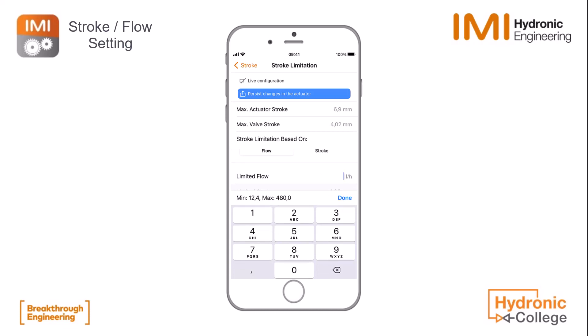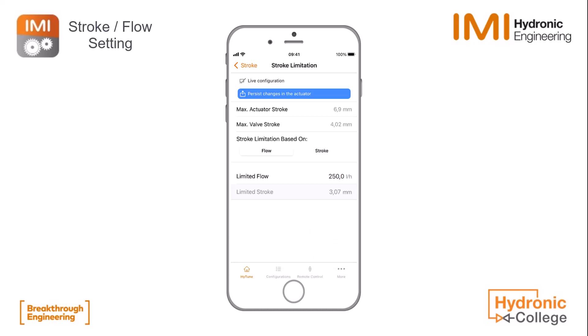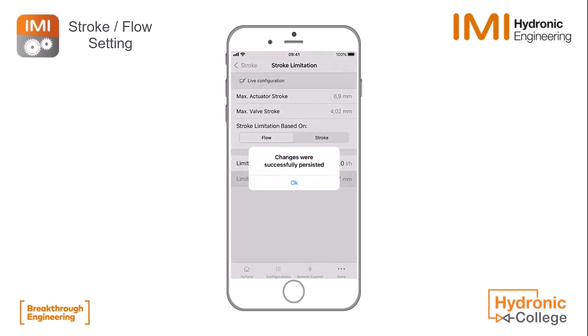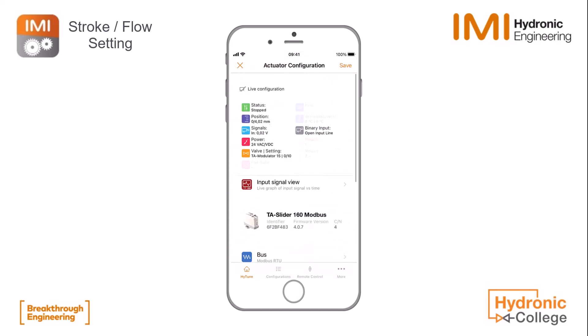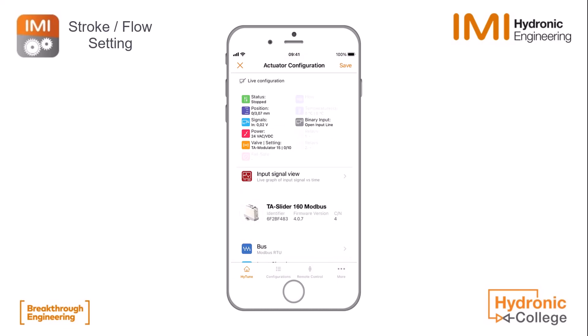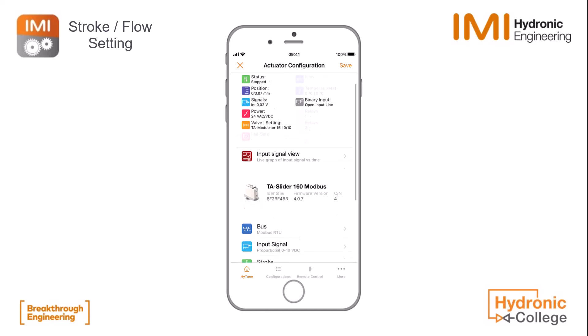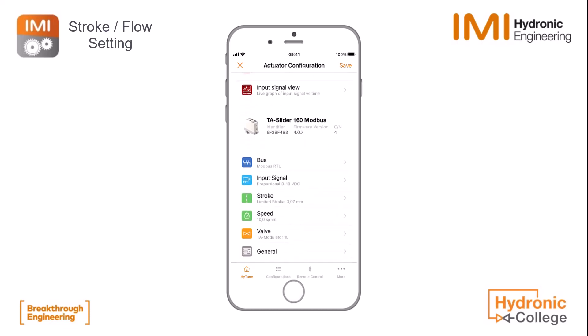So now we change to, for example, 250 liters per hour, and you see the minimum and maximum values appearing. The limit stroke is 3.07 millimeters, which is equal to a flow of 250 liters. We persist the changes to have everything saved correctly, and we see in the live screen that the maximum position is now 3.07 millimeters.